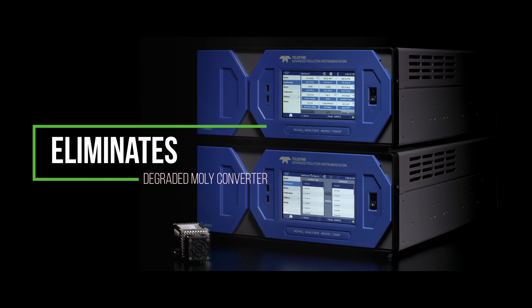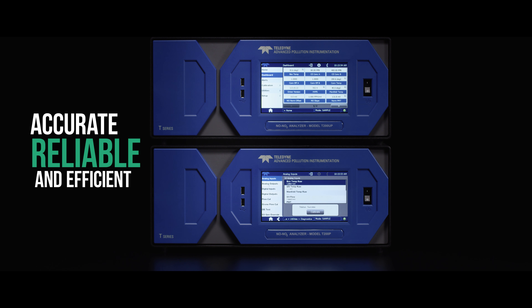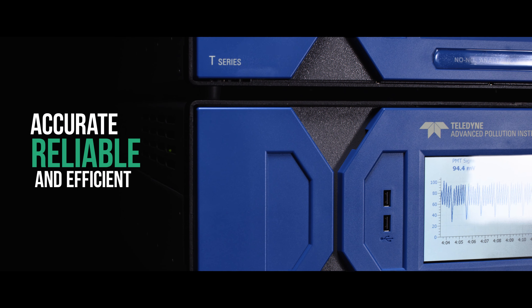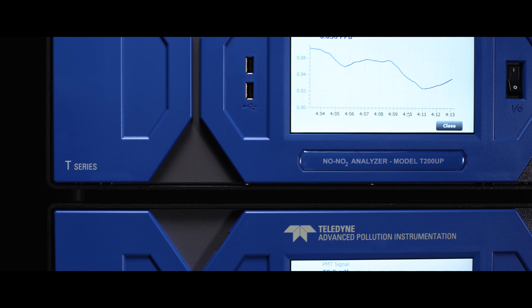This eliminates the need to replace a degraded molybdenum converter over time. As the demand for more accurate, reliable, and efficient NO2 measurements increases, the T200UP series fits this essential role, providing a more consistent and accurate NO2 reading.